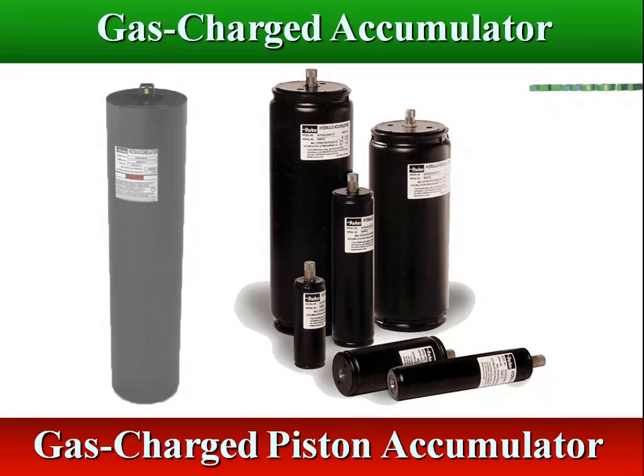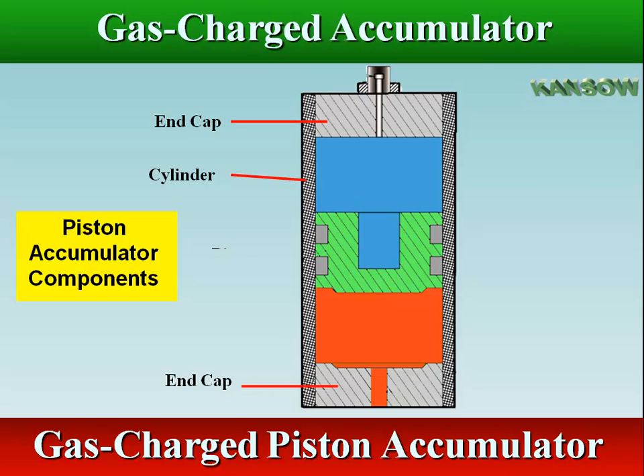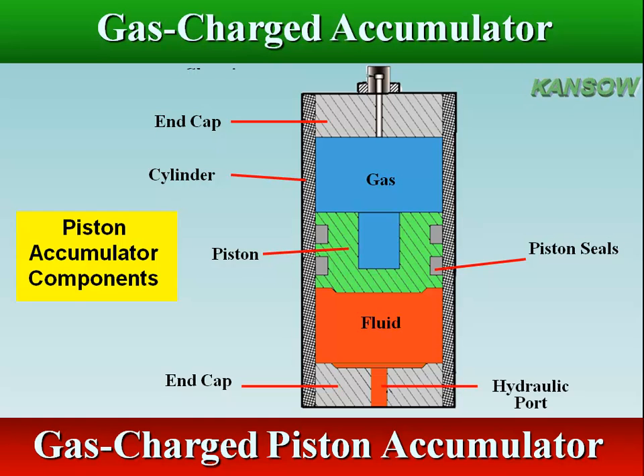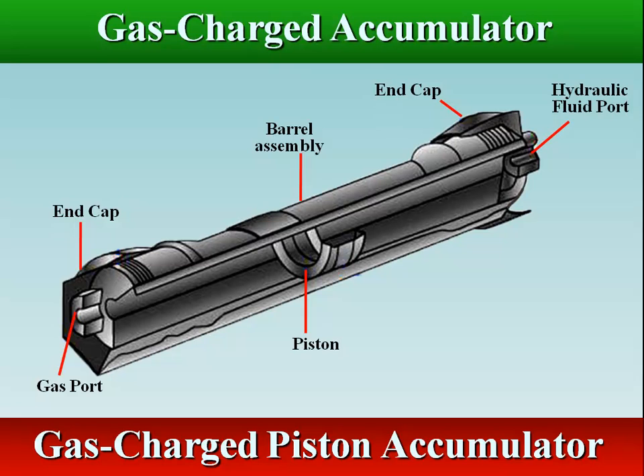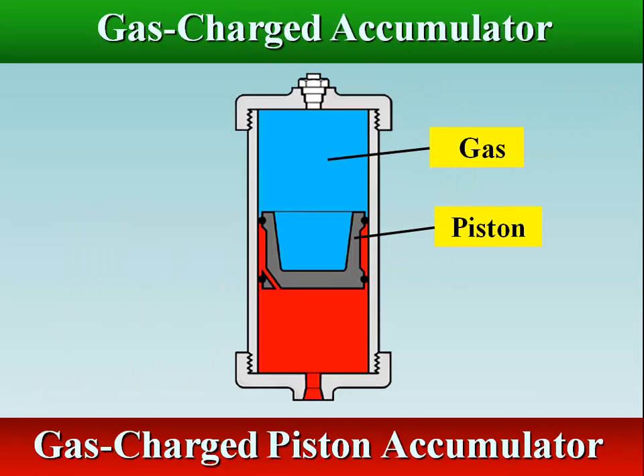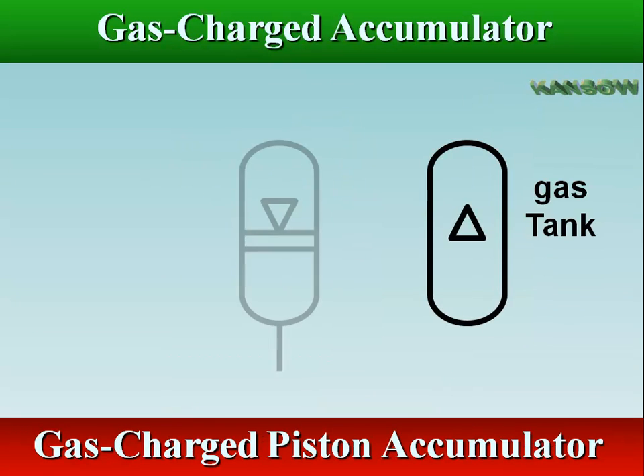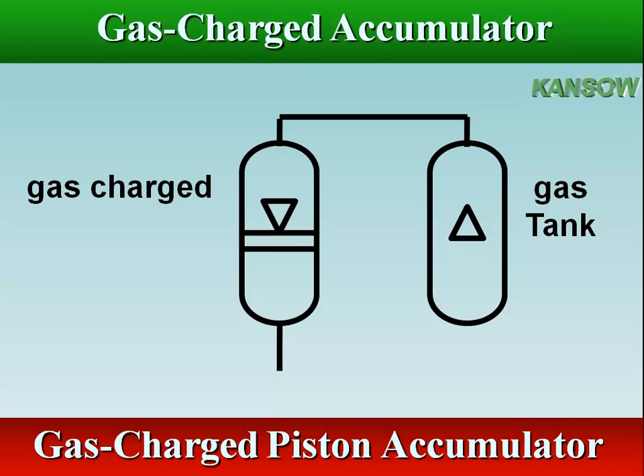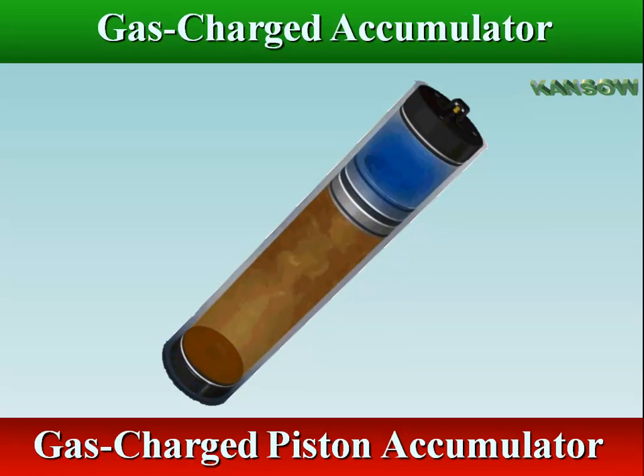Piston type accumulator consists of a cylinder assembly, a piston assembly, and two end cap assemblies. An accumulator contains a free-floating piston with fluid on one side of the piston and pre-charged nitrogen on the other side. An increase of fluid volume decreases the gas volume and increases gas pressure, which provides a work potential when the fluid is allowed to discharge.